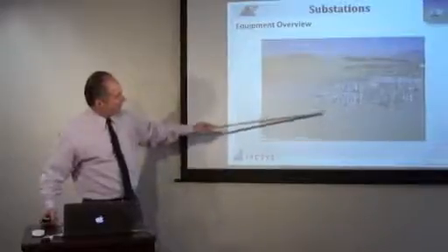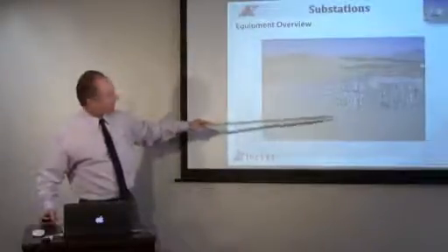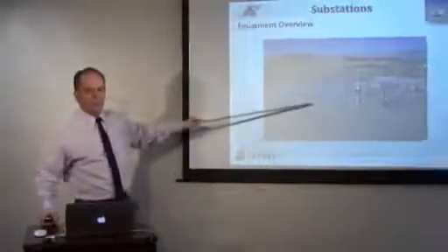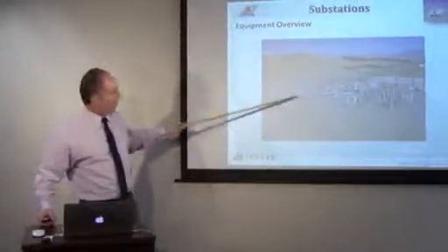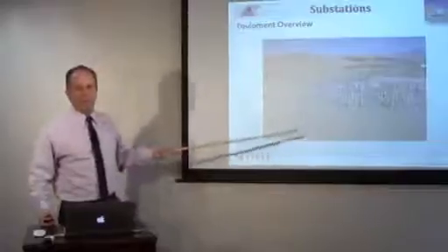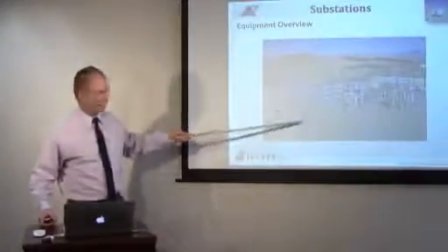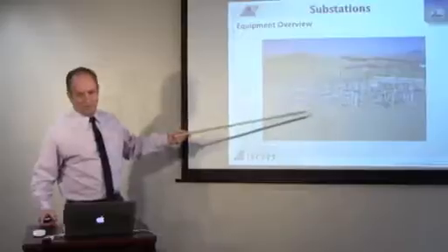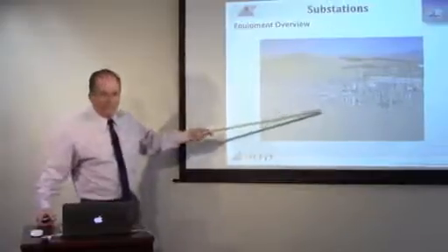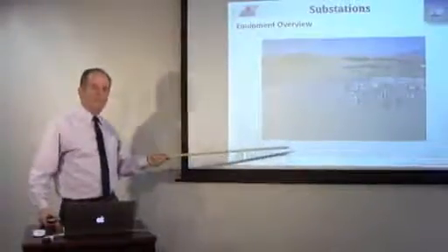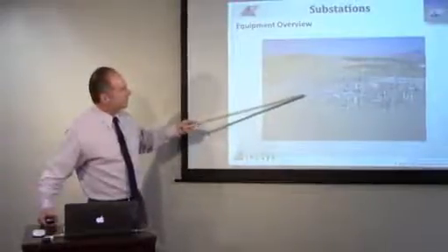And on these steel structures that are grounded, up above is the bus work, the aluminum tubing. Those are the three phases, and they're all aluminum. You don't get red, blue, green here in the real world. They're all aluminum, and they're either numbered 1, 2, 3 or A, B, C, sometimes colored with some tape. But the idea is it's three-phase.